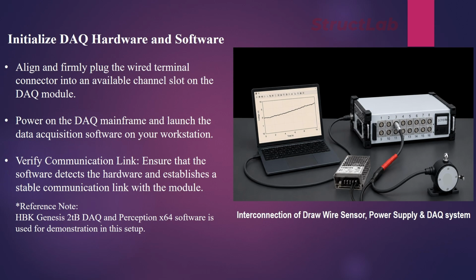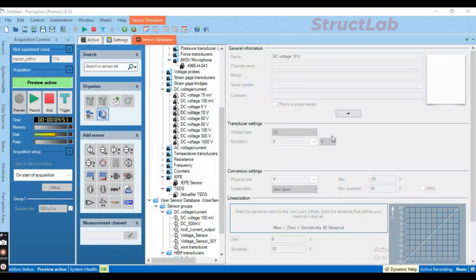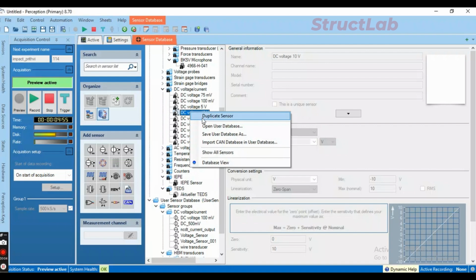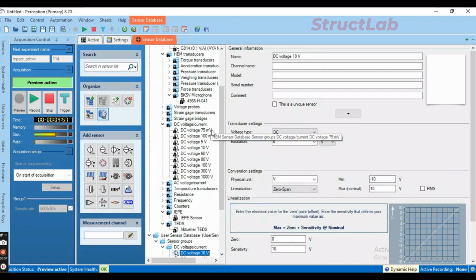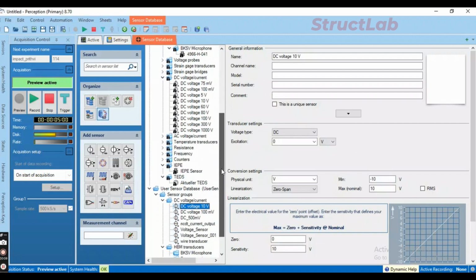Now let's switch over to the software interface to configure our draw wire sensor. First, navigate to the Sensor Database tab. In the database tree, right-click on the standard DC voltage 10V sensor template and select Duplicate Sensor. This creates a new customizable sensor profile. Select the newly created entry at the bottom of the list to open its parameters. Under General Information, rename the sensor, let's say Draw Wire Transducer, and the channel name as Channel_10.